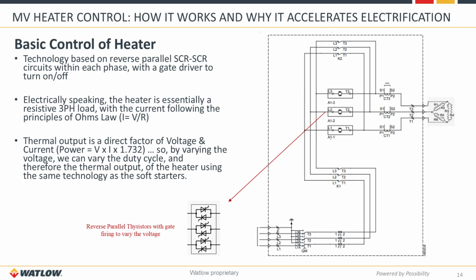So the technology is really based on Ohm's law, where, as many of you know, V equals IR, or the current going through the system is a combination of the voltage and the resistance of the heating element. Obviously, within a resistive heating element, though, you are trying to manipulate the power over a period of time. Within that period of time, you want a constant power output or vary by the duty cycle that you need to produce the power. Therefore, it's not just a soft starter type system. It's really a system where you are trying to provide power on a continuous basis.